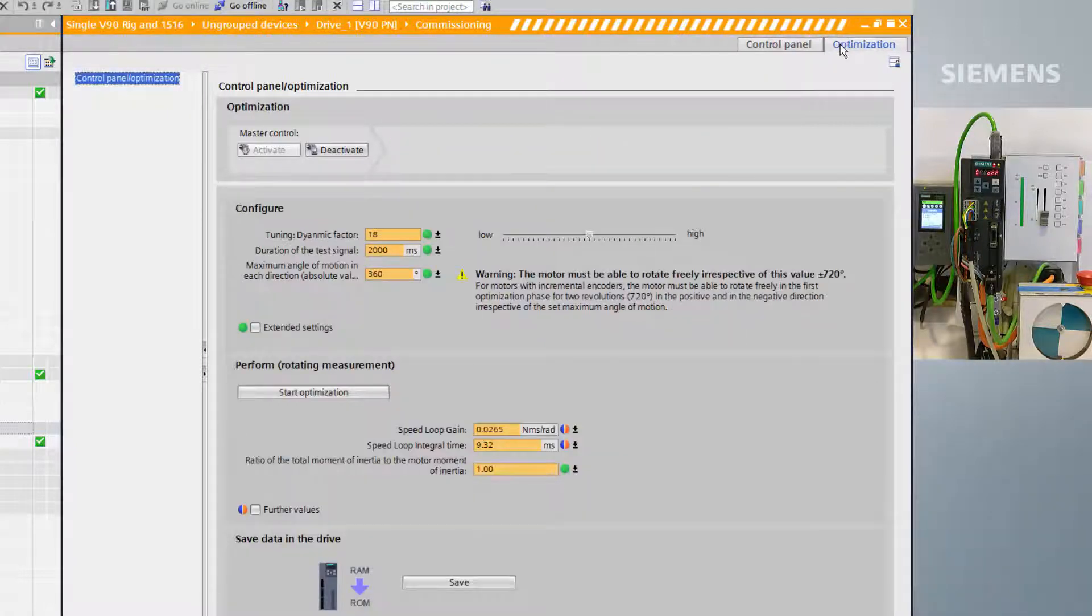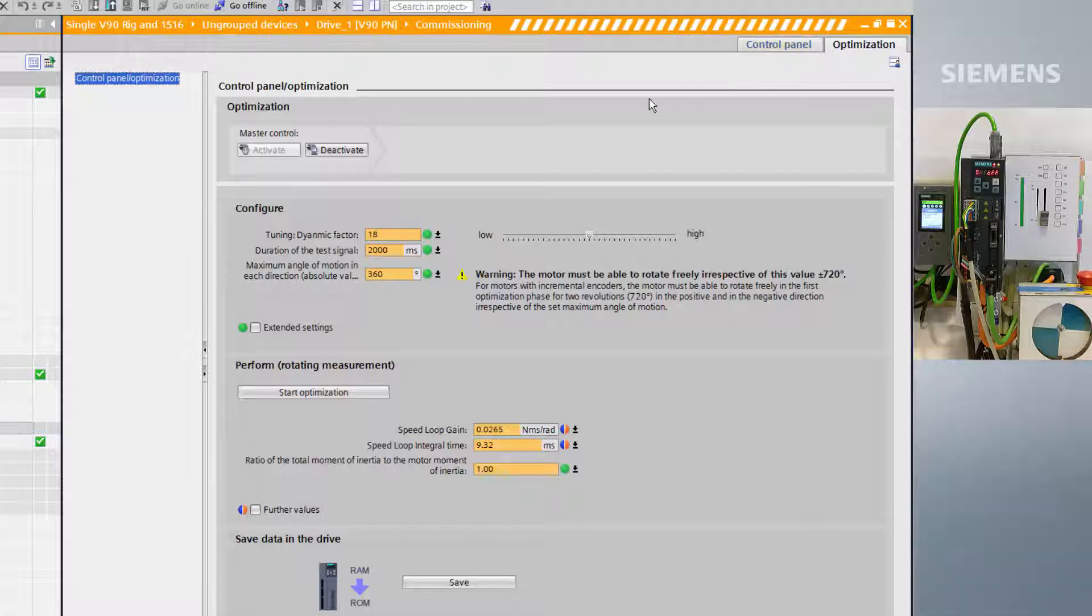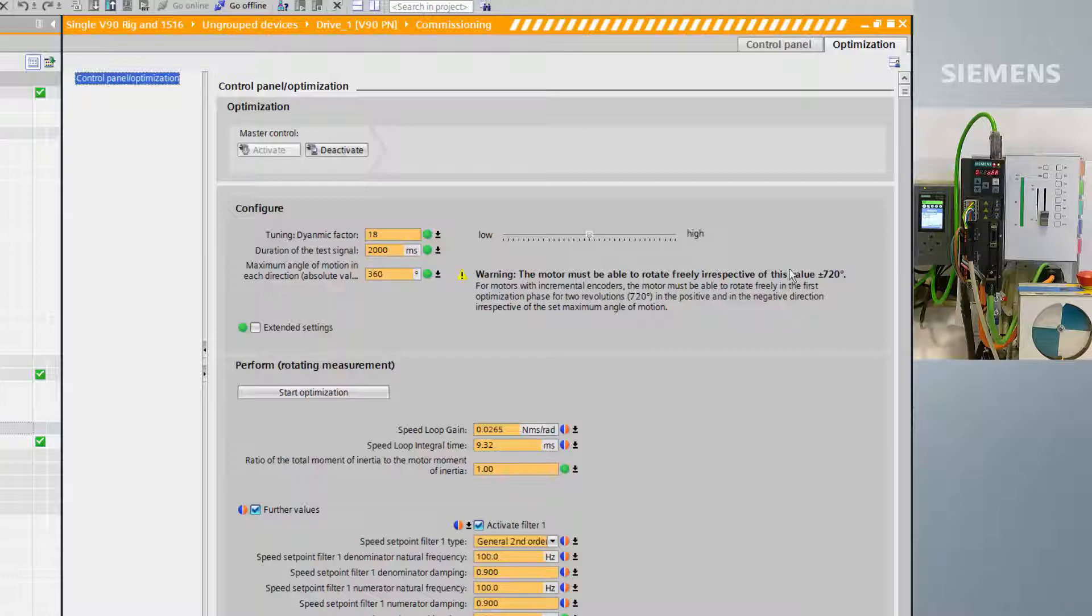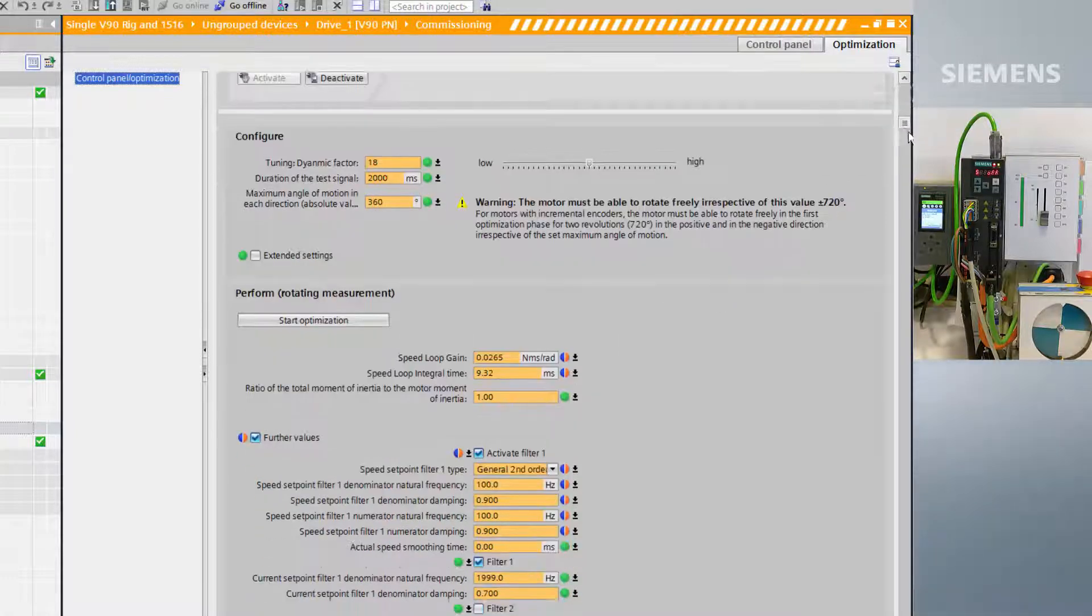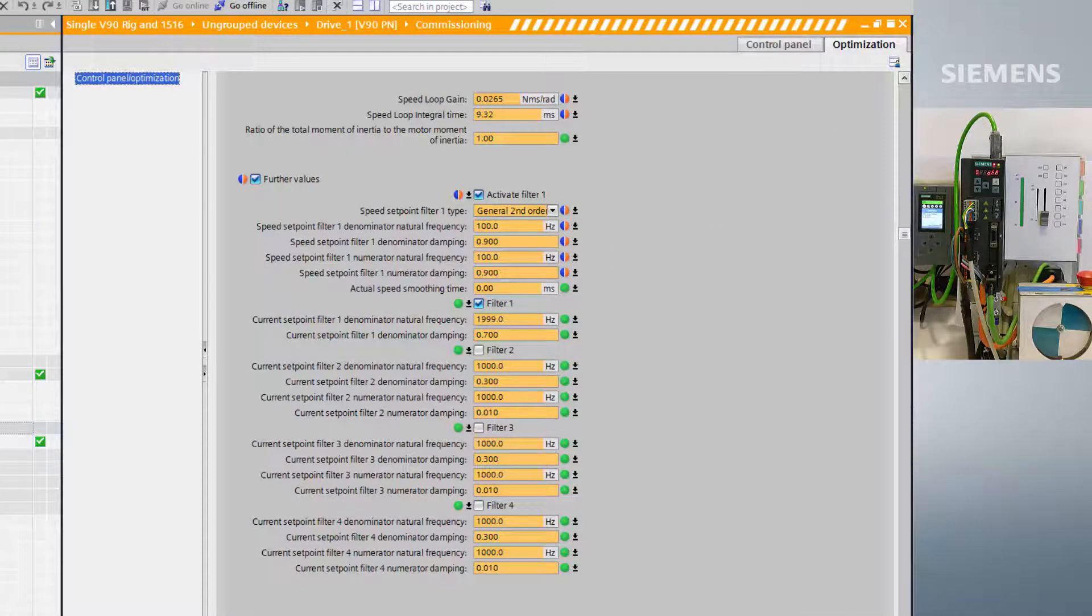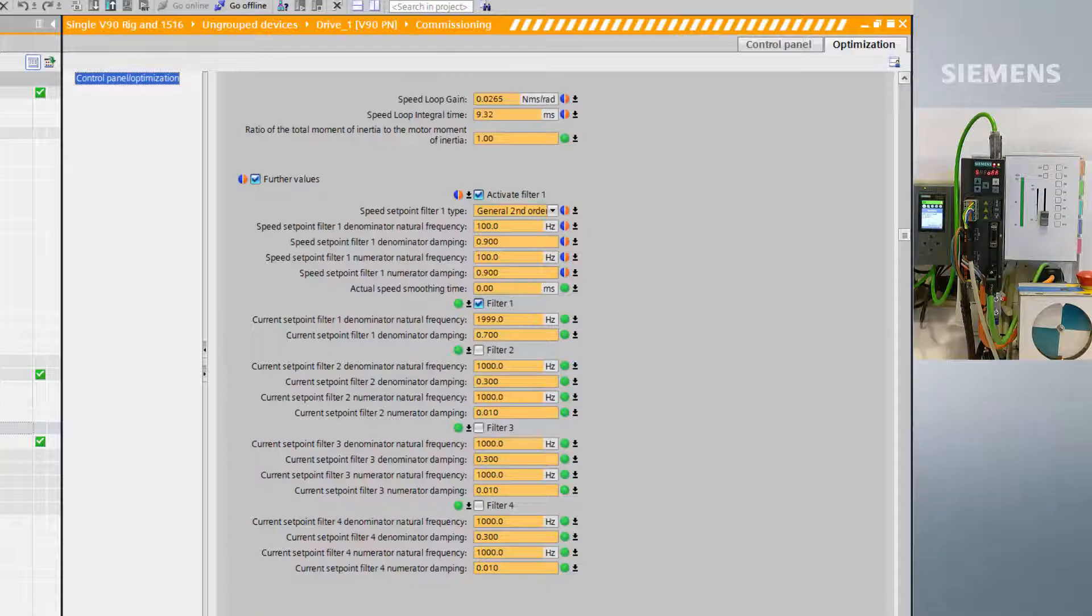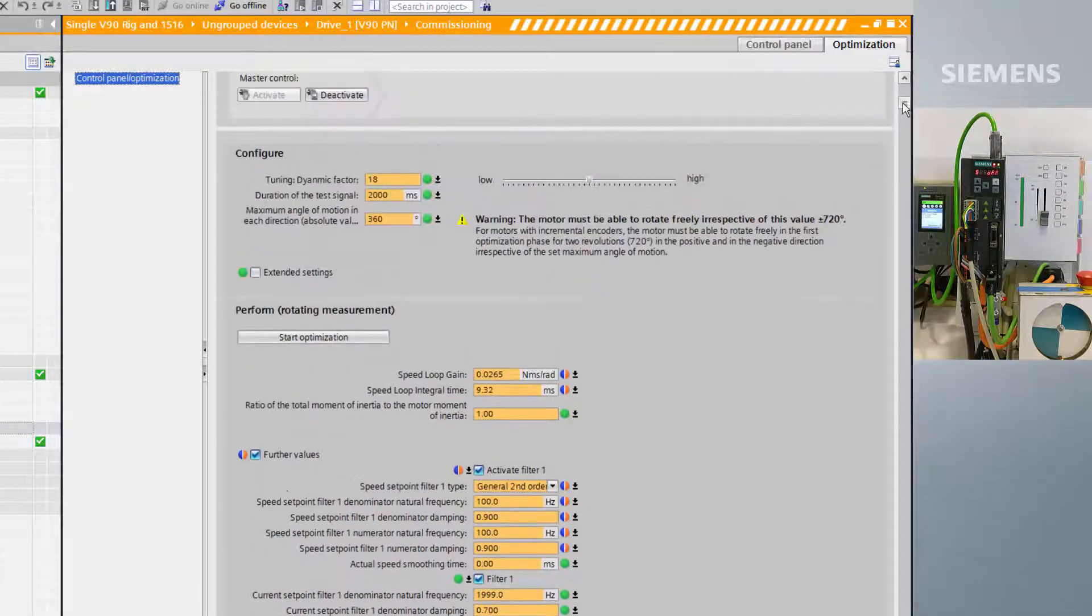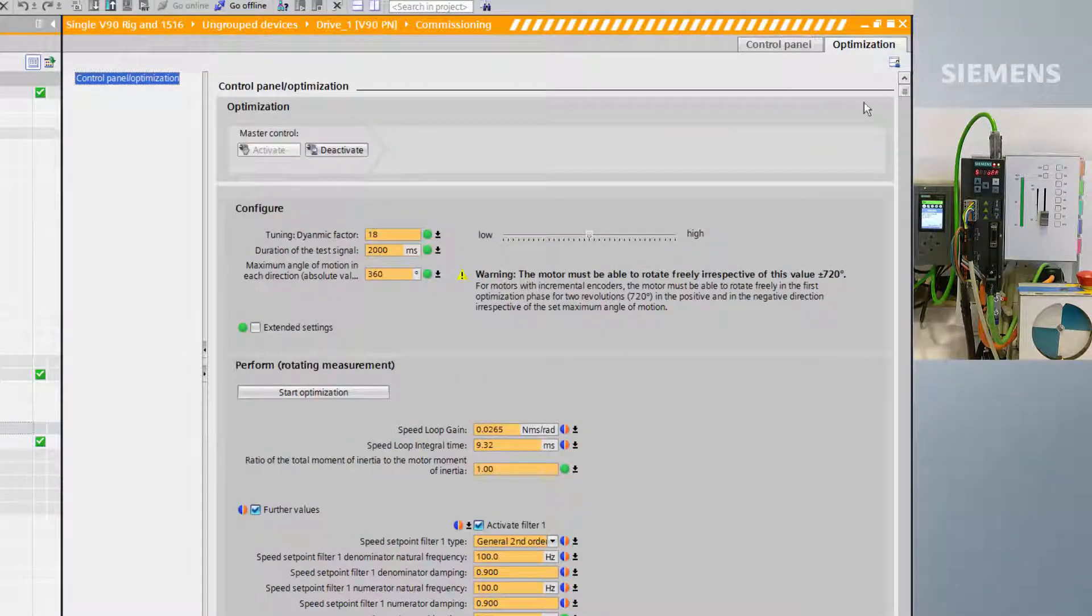To begin speed loop tuning, we go to the optimization pane. If we select further values, we can see all the factors that will be tuned. These will be different depending on the dynamic factor we have selected for our tune, which defines the responsiveness of the axis.